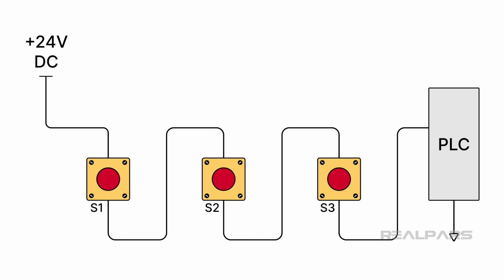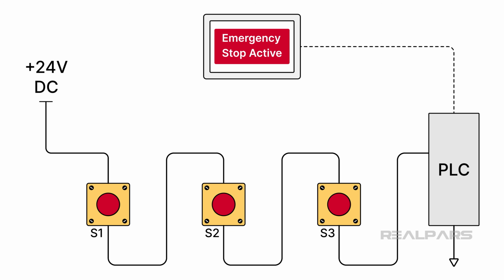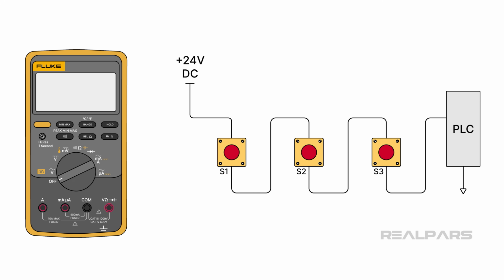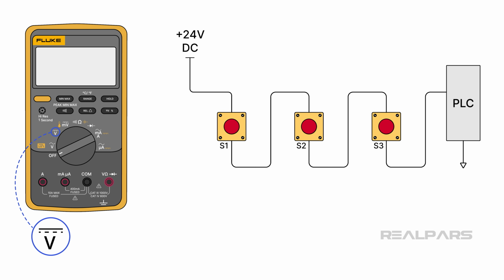Anyone who has studied series circuit theory knows that a break anywhere in the circuit instantly stops current flow. So, operating any of the series wired e-stop switches will trigger an emergency stop active alarm. But any switch failure or open wire can cause the exact condition. Time to do some troubleshooting. Let's start with our preferred live voltage troubleshooting method rather than the awkward continuity or resistance testing method.